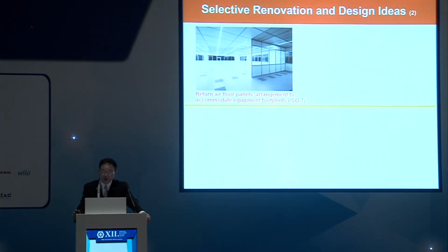This is the sometimes return floor panel. You may not need to use 100%. In this case, the return floor panel density is different. The reason for that is to house major equipment. Some equipment needs to sit on the floor, so if you put a return grill underneath, the return path will not be very good. So not all the return floor needs to be 100%. It's based on the classification and the application.